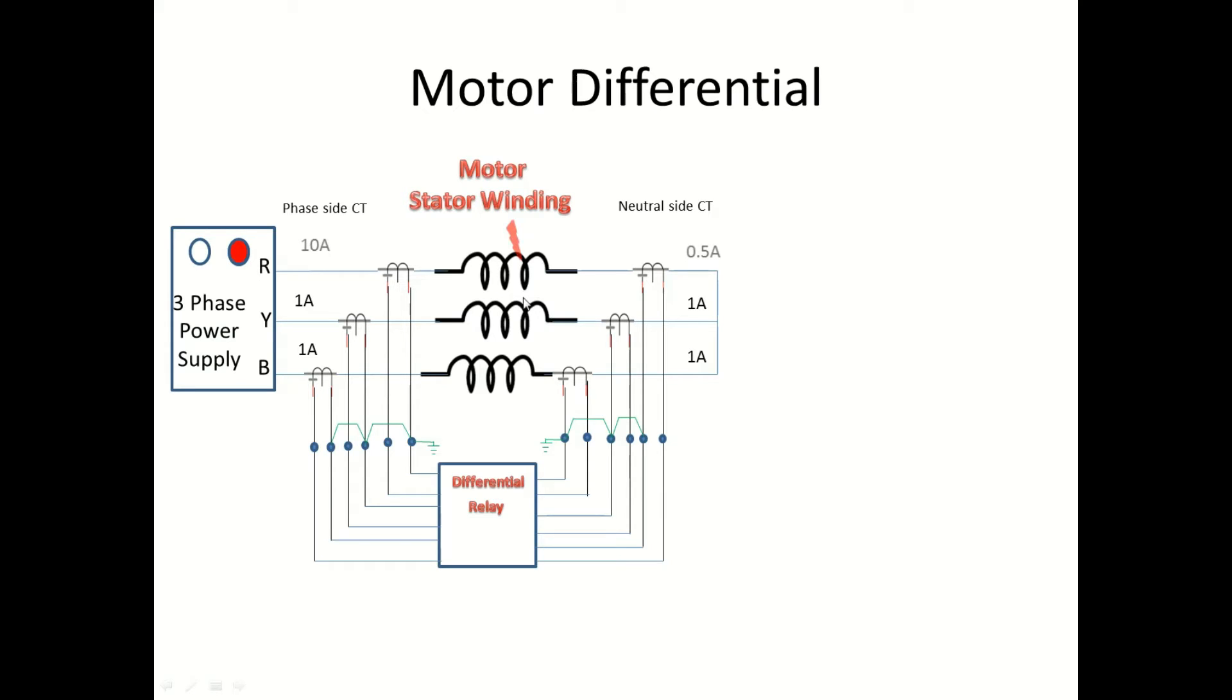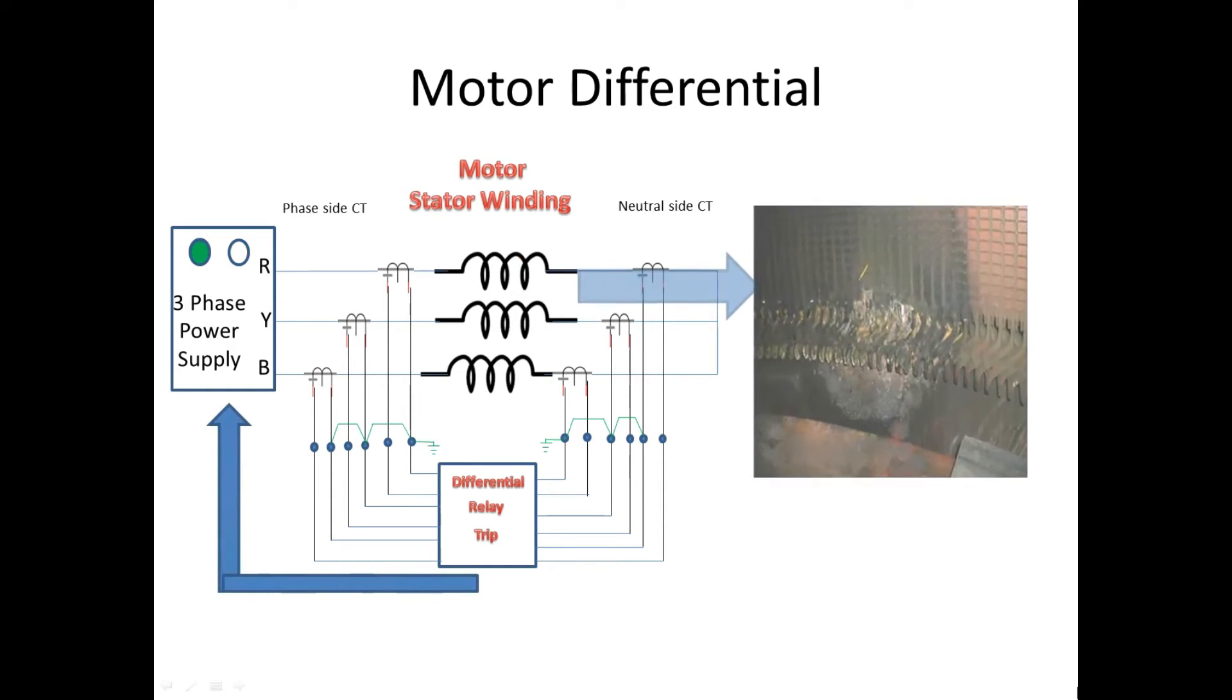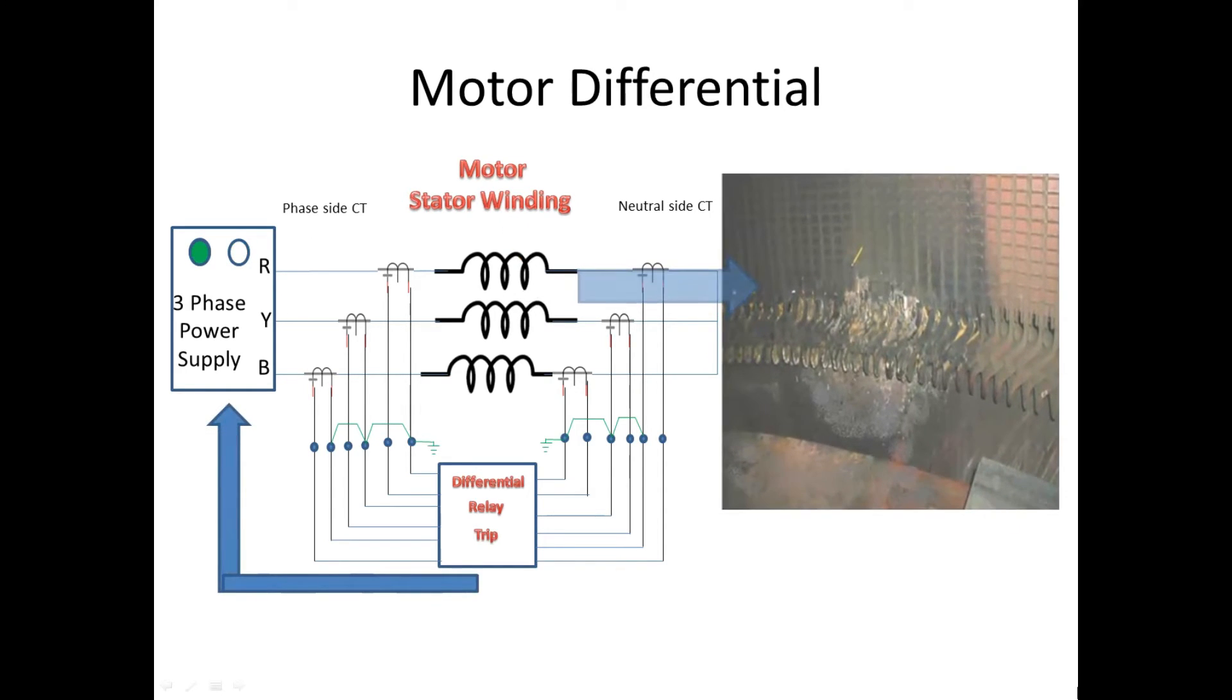And on the other side, the neutral side only takes 0.5A. So the differential relay senses the differential current and gives a trip to the breaker. Now the breaker trips and the power supply is cut. So the fault has been isolated from the beginning stage of the fault, like this.